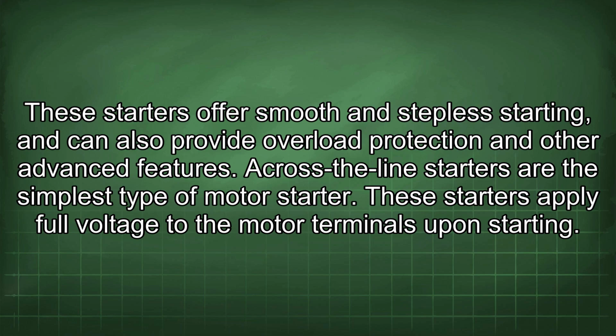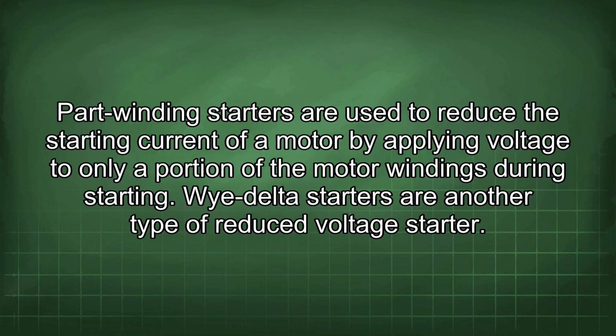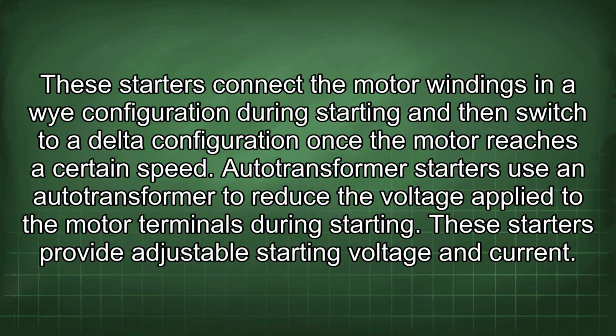Across-the-line starters are the simplest type of motor starter. These starters apply full voltage to the motor terminals upon starting. Part-winding starters are used to reduce the starting current of a motor by applying voltage to only a portion of the motor windings during starting. Y-delta starters are another type of reduced voltage starter. These starters connect the motor windings in the Y configuration during starting and then switch to a delta configuration once the motor reaches a certain speed.